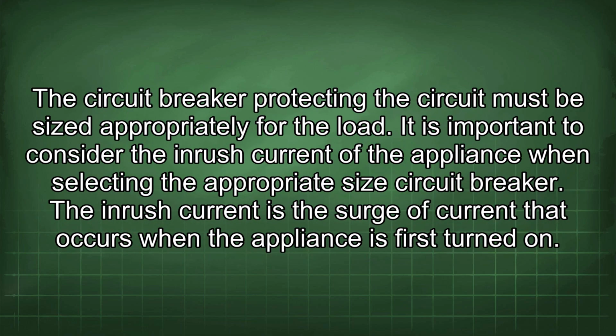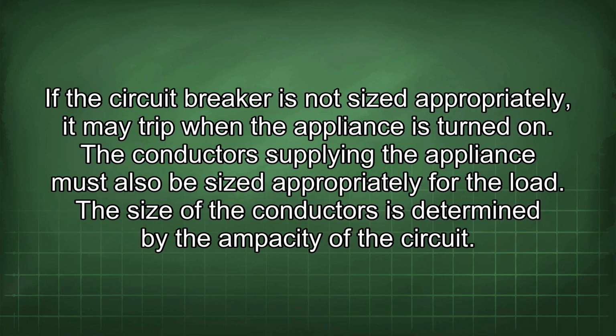The circuit breaker protecting the circuit must be sized appropriately for the load. It is important to consider the inrush current of the appliance when selecting the appropriate size circuit breaker. The inrush current is the surge of current that occurs when the appliance is first turned on. If the circuit breaker is not sized appropriately, it may trip when the appliance is turned on.